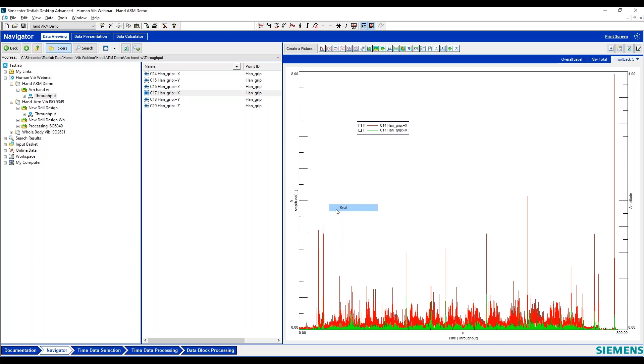And now what we want to go over to is time data processing. And we'll select all 3. And if you go under section, there's going to be a tab called level calculation. And this is where we want to go. And we'll go down here and we'll select RMS, hit add, and make sure you have the right group selected, in this case vibration, makes sense for us. Hit OK, and we will calculate it.